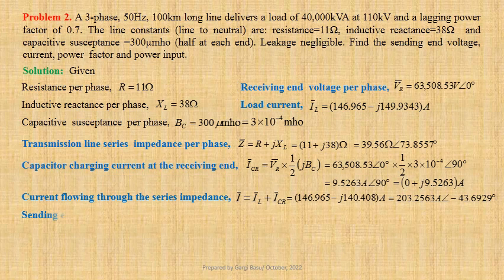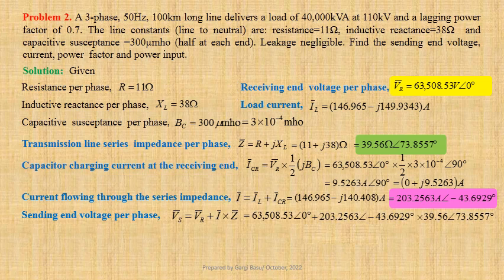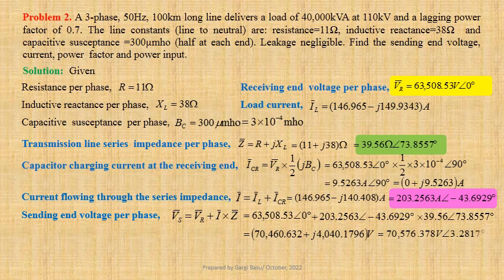Now we shall determine sending end voltage per phase. Vs equals Vr plus I times Z. Using values: 63,508.53 at angle 0° plus 203.2563 at angle −43.6929° times 39.56 at angle 73.8557°, that gives us 70,460.632 plus j times 4040.1796 volts. This may be written in polar form as 70,576.378 volts at an angle 3.2817 degrees.